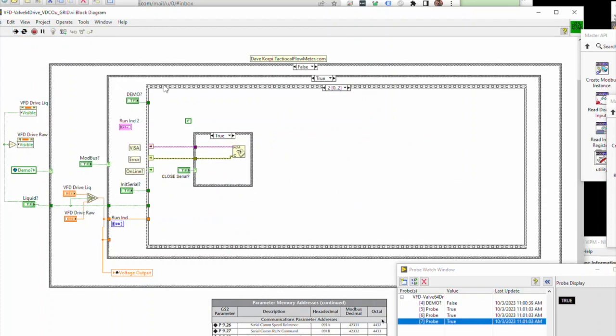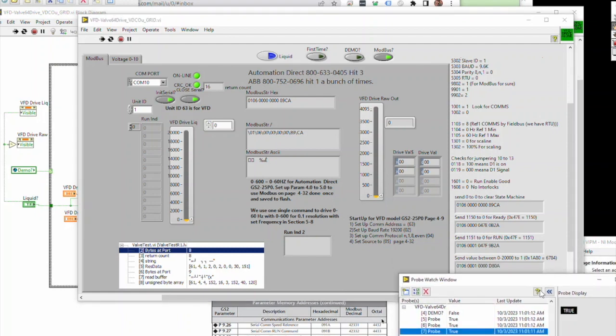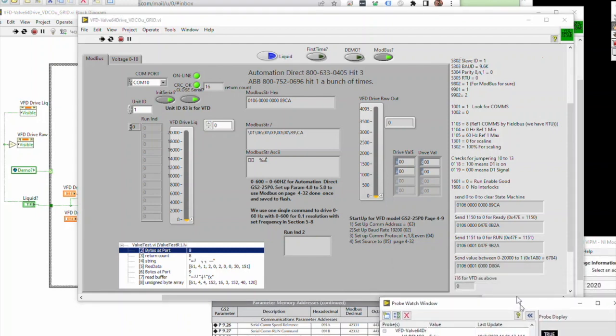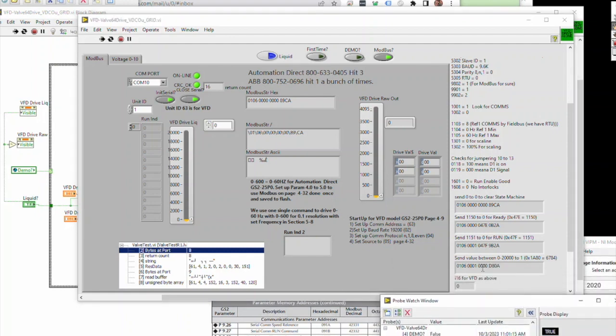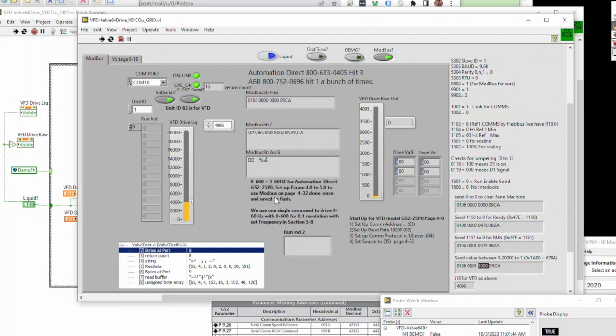Now I'm going to look. I'm going to set something like 4096. We want to be looking at this value here. This is sending address one, function code six. We're sending a one apparently to here. So I'm going to send 4095, which will set the frequency to zero FFF. And if I get a 4096, it'll be 1000. So this sets the frequency.